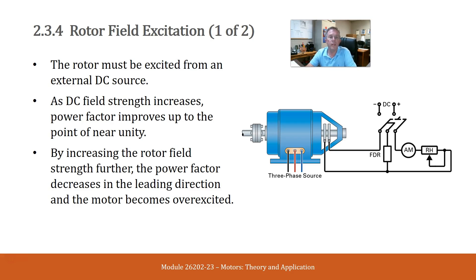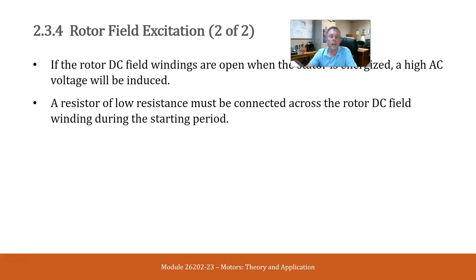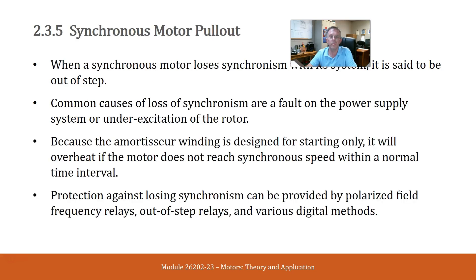Rotor field excitation. The rotor must be excited from an external DC source. As DC field strength increases, power factor improves up to the point of near unity. By increasing the rotor field strength further, the power factor decreases in the leading direction and the motor becomes overexcited. If the rotor DC field windings are open when the stator is energized, a high AC voltage will be induced. A resistor of low resistance must be connected across the rotor DC field winding during the starting period. When a synchronous motor loses synchronism with its system, it is said to be out of step. Common causes for loss of synchronism are a fault on the power supply system or under-excitation on the rotor.